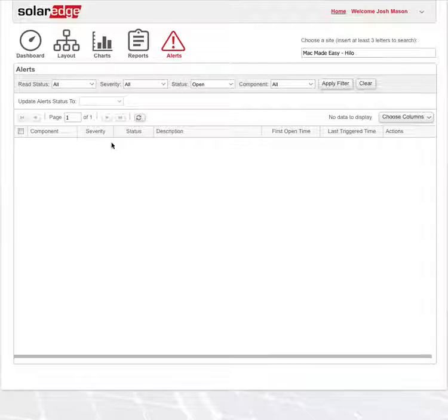All these things could produce a report that seems severe, but in reality they'll resolve themselves in a short period of time. It's when you have a long-lasting issue either affecting production or monitoring capabilities because of communication, or because one of the optimizers is reading out a failed module or a degraded module. Those are the instances that you want to take action in order to resolve the issue quickly, in order to bring system production back up to maximum.